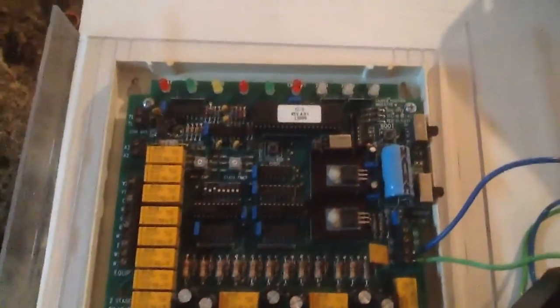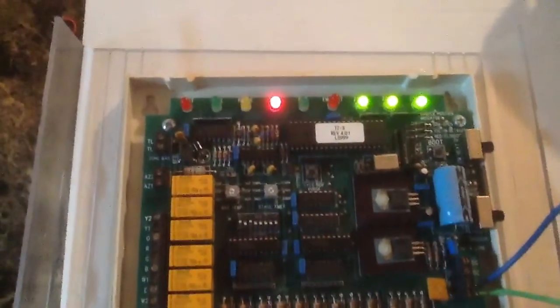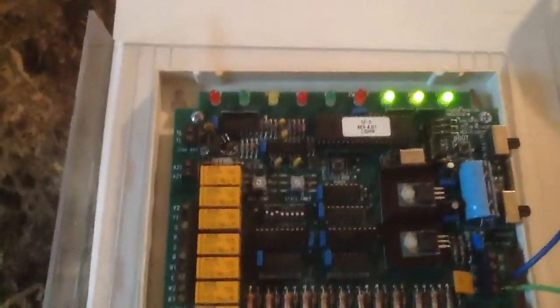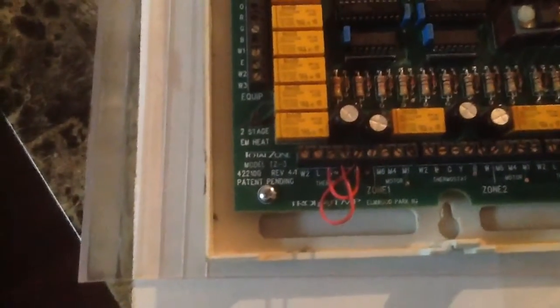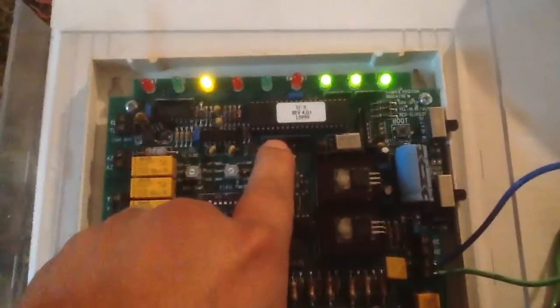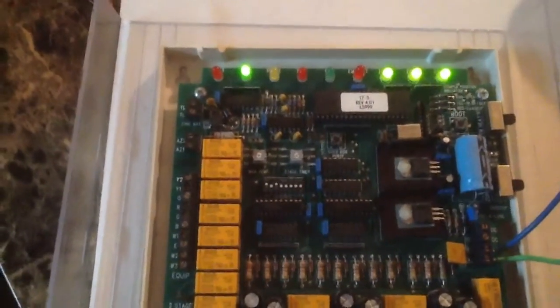So basically that's it, and we'll show you how this one over here runs. I actually have this one wired up to a transformer and to this little thing right here. You see? So that's what you'll typically see on this thermostat, and it'll blink idle, and then in a couple of seconds it'll hit purge, and it's just going through its time delay. And what I have here, I have R and Y1 and G jumped out, so it's like a call for cool. See? And if I want to speed it up, I hold that. Here we go. And we've got a call for cool.